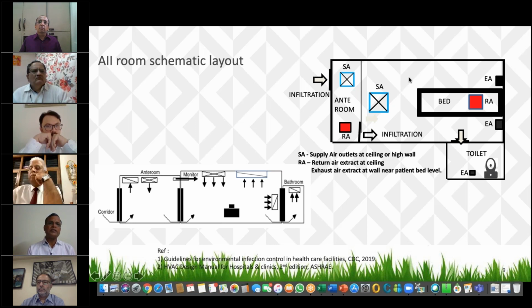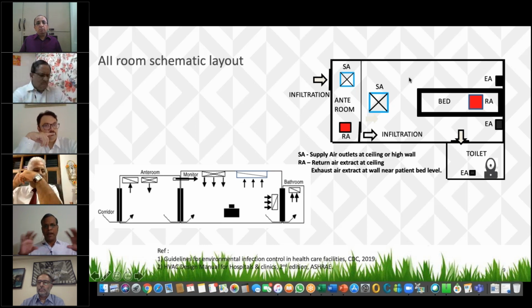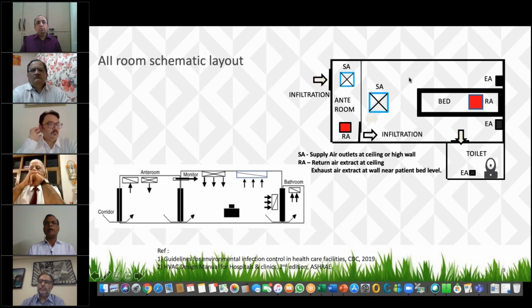And the flow pattern of air inside a COVID patient room will also have to be such that the air moves from other parts of the room and is directed towards the patient. As the patient coughs or sneezes, as the plume of droplets comes out, we would want to position the exhaust at a point reasonably at bed level, and something at the ceiling right above the patient. So whatever droplets are there can be immediately exhausted or removed from the room so that they don't spread out into the room. This is basically the schematic suggested by both CDC as well as ASHRAE. So this is a proper designated airborne infection isolation room for COVID or any airborne infectious disease.